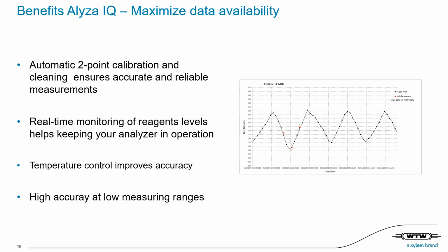Furthermore, the Alyza temperature control package, which is aided by 4 different temperature sensors, helps to keep the temperature inside the unit tightly controlled. The result is high accuracy, especially at the low end. So in the graph, you can see measurements of an Alyza IQ with measurement range 1 over several hours in black at a 10 minutes interval. In red, you can see lab comparison measurements, and you can see how accurate the ammonium analyzer measurement is compared to the lab measurement. Both are using the same standard method.